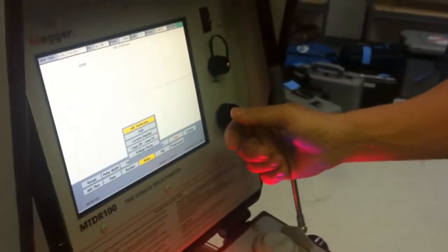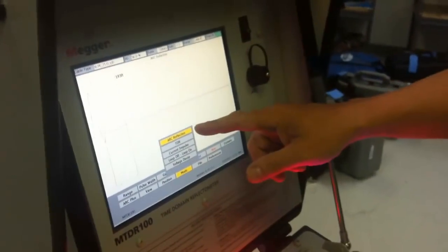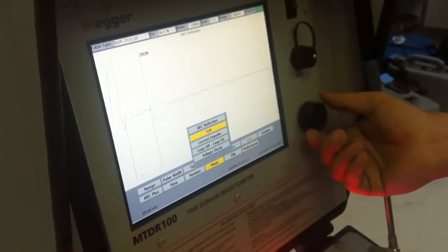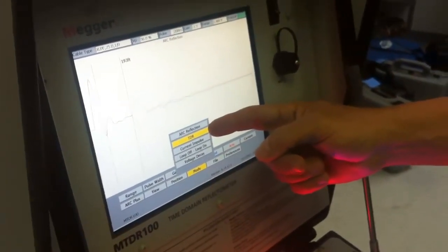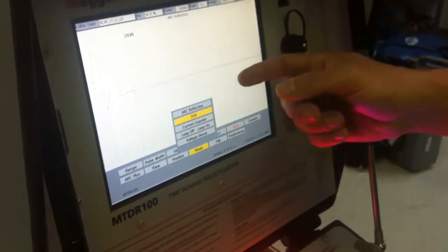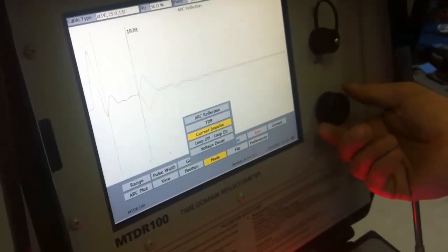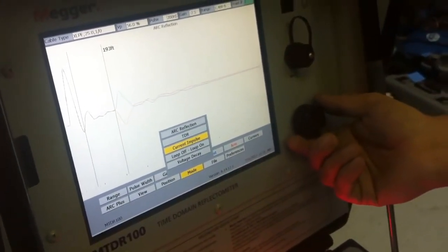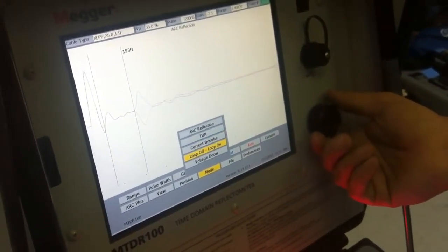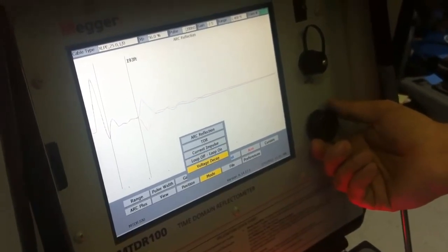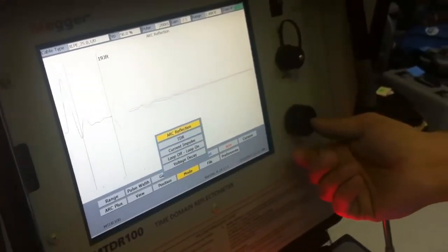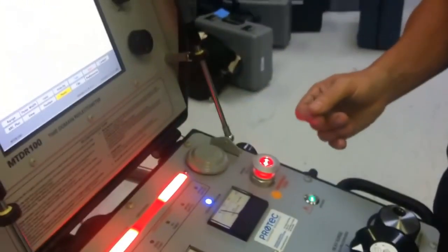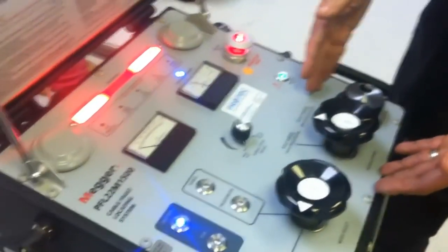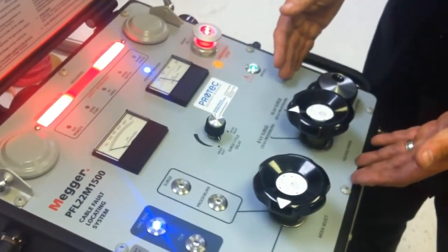Modes of operation. Here's where I can change the radar from the arc reflection style radar to just low voltage TDR, which will allow me 3 waveforms, one for each phase of the circuit. I can do the impulse current technique, a technique referred to as loop off, loop on, and also voltage decay. So again, a rather simple user interface, very intuitive, combined with a rather simple high voltage user interface, rather intuitive.